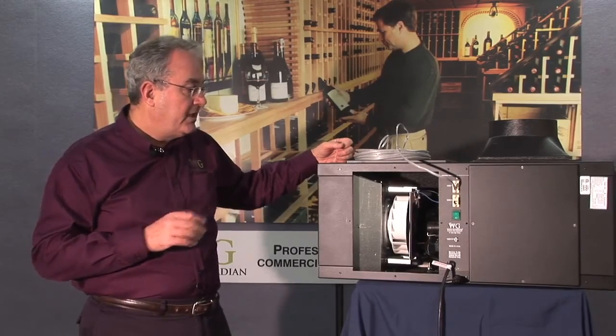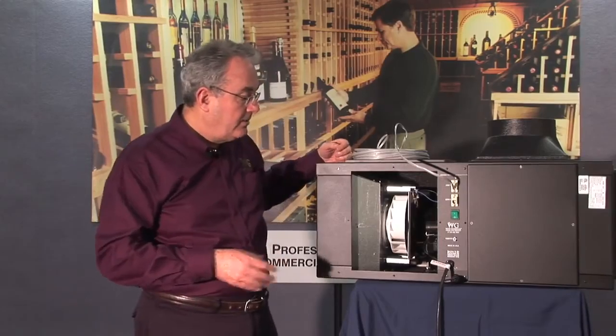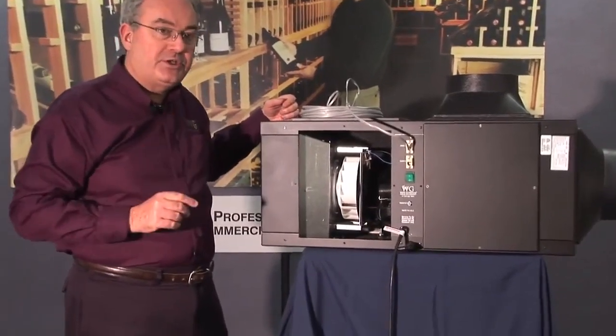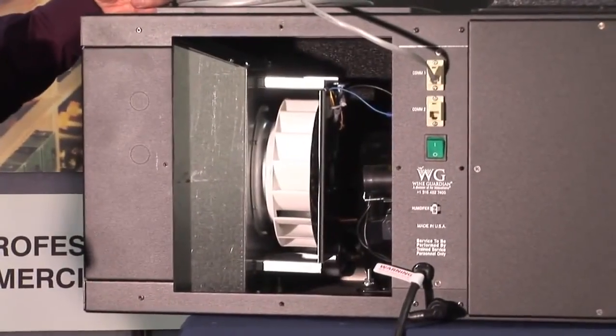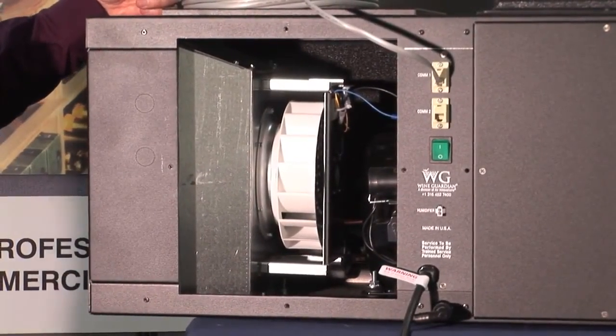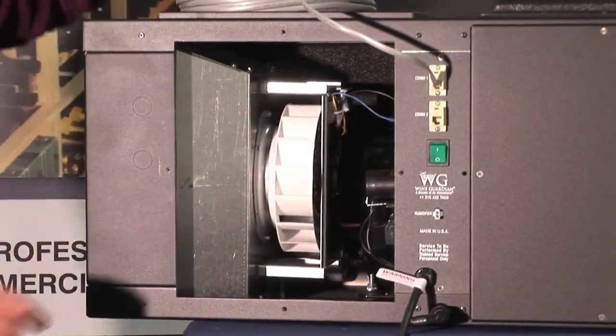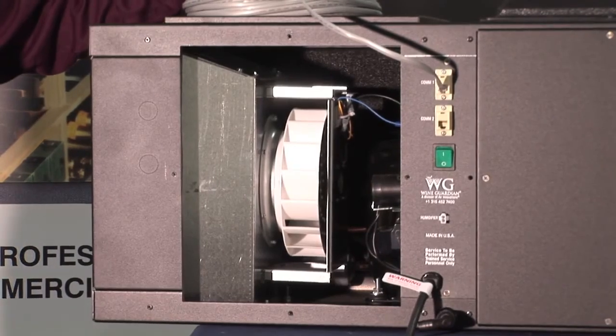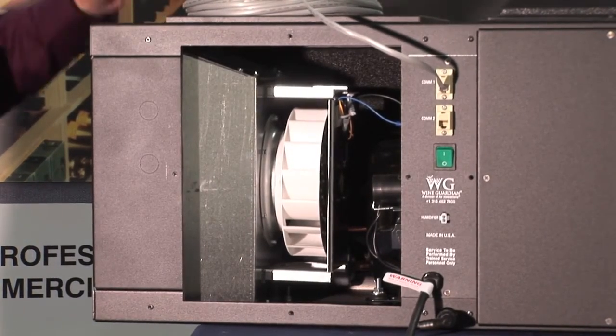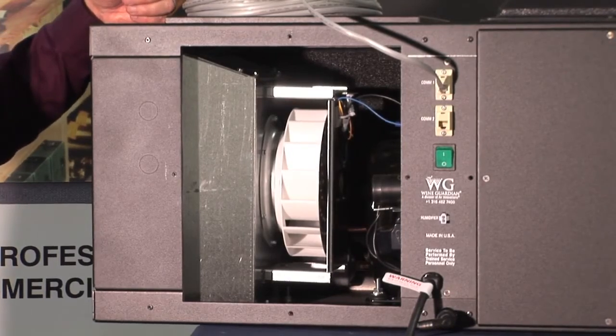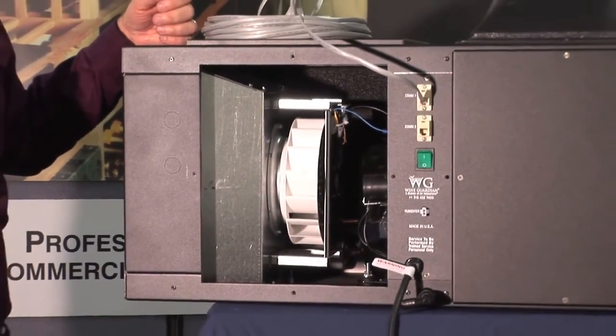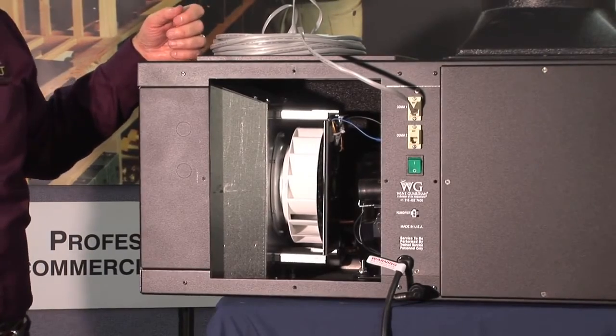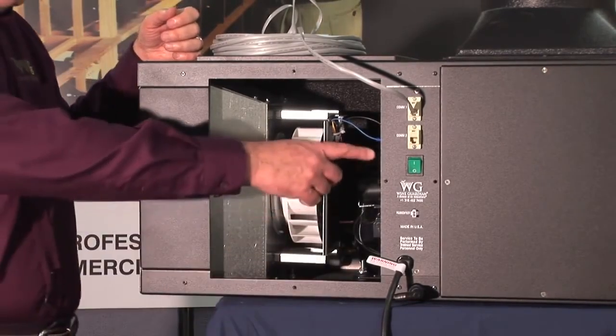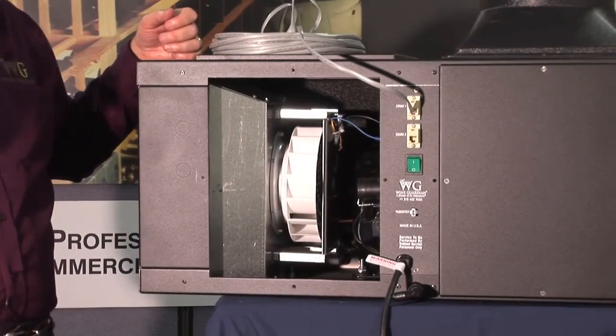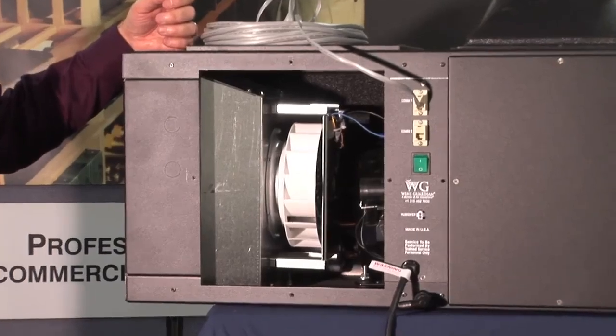You don't have to have any kind of service technician actually next to the wine collection when they're working on the units. So taking a look back inside at those commercial grade components, you do see the compressor in here. There is a high pressure switch in all of these units. It's actually accessed from the other side of the unit, but by removing the panel, it's very easy to get to the high pressure switch. You see that there are two communications ports here. This one is now configured for the remote interface. It's possible to use the other communications port to install remote sensors. This unit can use up to 3 sensors within the space to monitor and average temperature and humidity conditions. That's particularly important in a very large wine cellar. Notice the on and off switch, the humidifier connection if the freestanding remote humidifier is used.